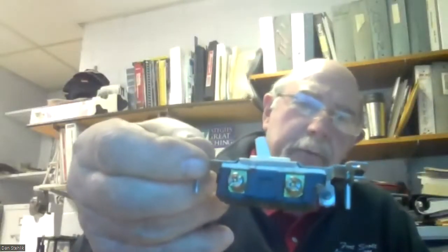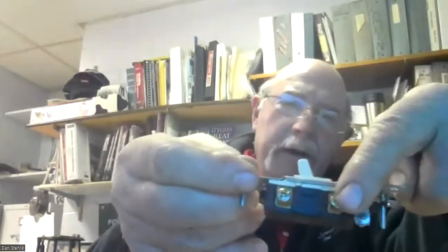On the switch, you've got 2 gold screws. Black wire goes to gold screw, one in and one out. The white wires, you're going to wire nut together. And although we have a metal box, we're just going to wire nut the grounds together. We're not going to attach the box to the ground wire.